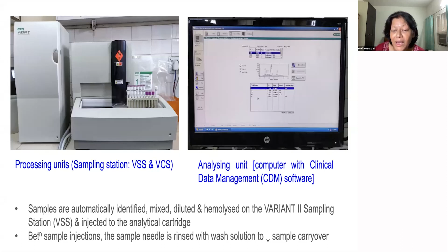Now, this is how the instrument looks. The instrument has the processing unit, which is known as the sampling station, and the Variant 2 sampling station is known as VSS. What is getting analyzed as peaks over here, you can see, is the analyzing unit. Basically, the computer has a clinical data management software, which is known as the CDM. What is important to remember is that between each run, the sample needle has to be rinsed and washed with the solution so that there is no sample carryover. I'll briefly show you an example of how sample carryover looks.